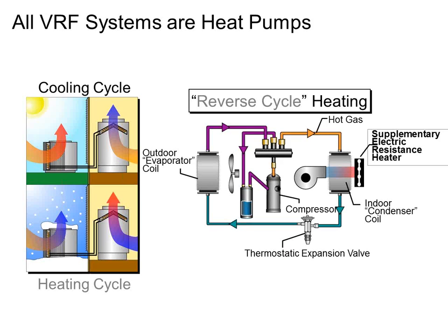If I have electric resistance heat, all of the energy that I buy is being converted into heat, with the exception of a very small portion which gets converted to visible light, like when you look in your toaster and you see that little orange glow, right? So there's 0.1% of that, 99.9% is going into heat. In the case of a heat pump, I'm not burning anything to make heat. I'm only paying energy to move heat around. I'm not making heat, right? Furnaces, rooftops, boilers, electric heaters, they burn something. They convert a fuel into heat. Heat pumps do not convert anything into heat. They just pump heat around.